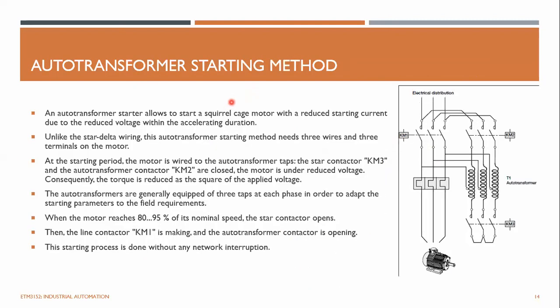Right, so the auto transformer start is another method of starting an induction motor with reduced torque and reduced starting current. An auto transformer starter allows you to start a squirrel cage motor with a reduced starting current, as I mentioned, allowing a reduced voltage within the acceleration duration. In the star connection, we know the 230 is applied, but in the auto transformer, there's a tapped connection. So you can adjust this auto transformer tapping and set this voltage to a desired level, right?